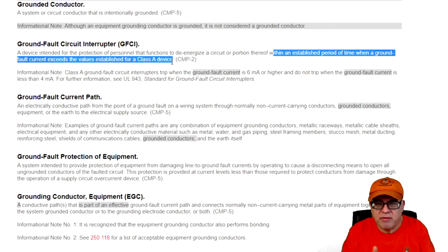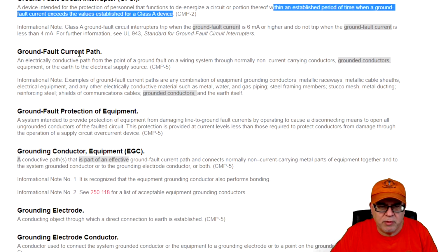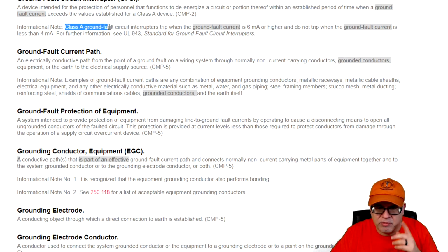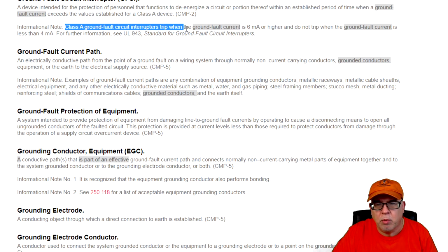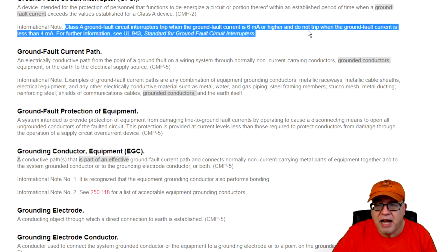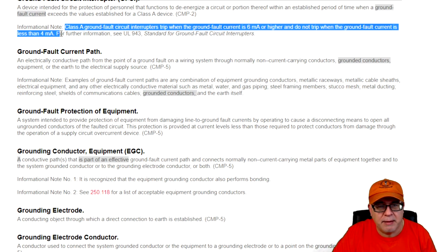But the code tends to talk about it, as you see in the informational note, based on UL 943. Let's look at the informational note, because that's the best way to look at it. It says a Class A, which is what we're talking about, what you're generally going to see in your kitchen countertops, bathrooms, that's a Class A. It says ground fault circuit interrupters trip when the ground fault current is 6 milliamps or higher, and do not trip when the ground fault is less than 4 milliamps, okay?